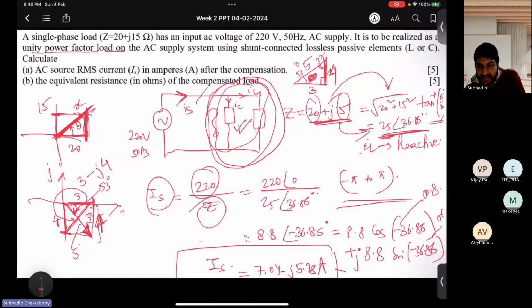So use geometry in this kind of problems. If you use geometry, then it will be very easy. So everyone got up to this? It is before compensator. This is the current, right? Yes, sir. So before compensator, this is the current. So what is the reactive current? 5.28 amperes. This was being drawn by the load, which was leading to non-unity power factor at the supply end.